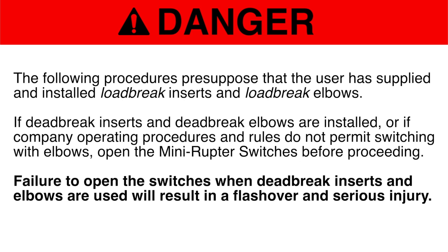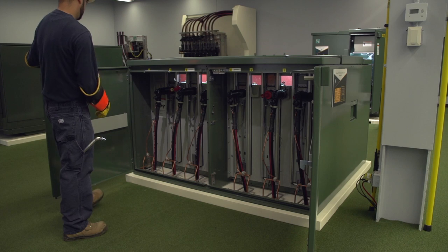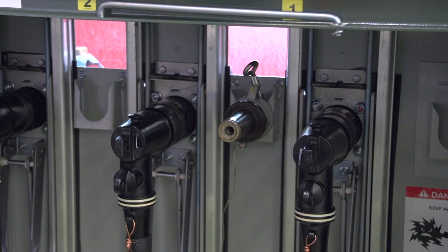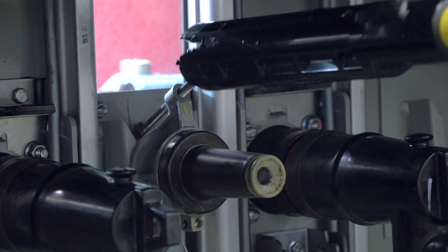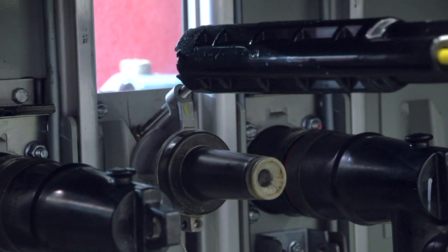Failure to open the switches when deadbreak inserts and elbows are used will result in a flashover and serious injury. To access the fuses, first open the enclosure doors. Then, using a shotgun stick, install a portable feed-through or stand-off insulator on the parking stand that is directly above the cable guide of the elbow to be moved. This will ensure that once the elbow is moved, the cable will not interfere with the transfuser mounting.